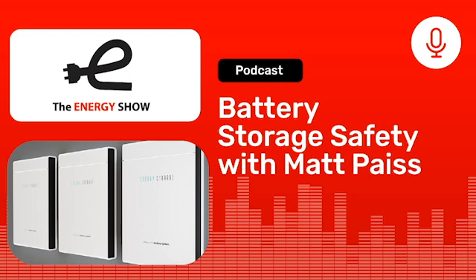If you do have fire coming out of the box, on residential batteries the test actually requires that you don't have any fire coming out of the box if the battery is going to be mounted on a wall. That's very challenging for current lithium-ion technologies, because they do often produce fire or flammable gas.